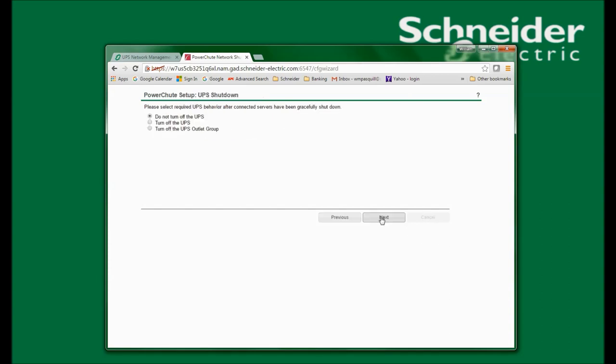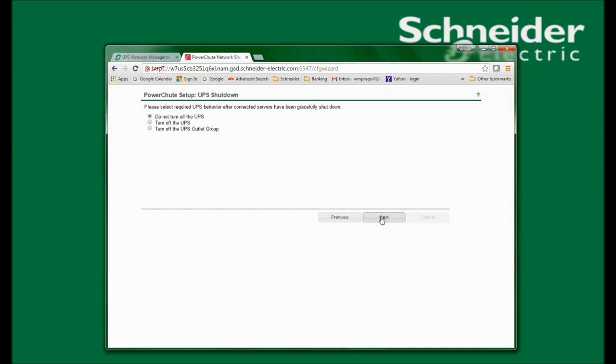In this window, I am given the options of do not turn off the UPS, turn off the UPS, or turn off the UPS outlet group. The reason for this is, if you would like your system to start automatically after a power failure, the UPS must first cut power to the outlet group before the system will restart. The system restart is set in the system BIOS — we have a KBase article on that if you would like further information. I will select turn off the UPS. This way, when power is restored, the UPS will turn itself back on and then restore power to all of the outlet groups. And click Next.